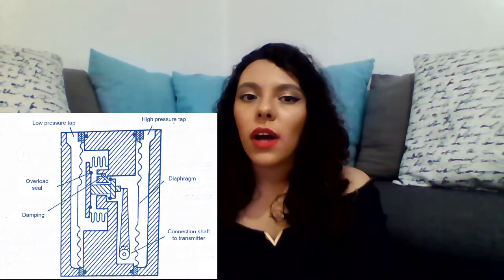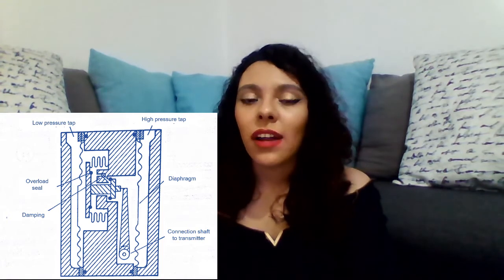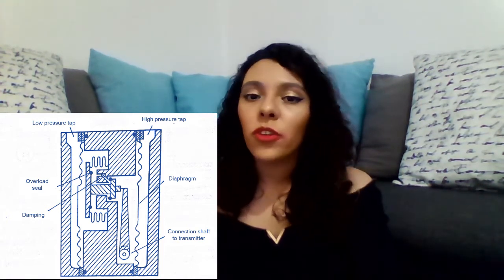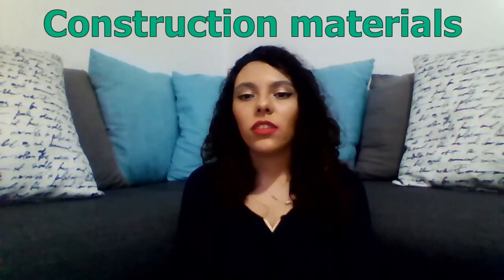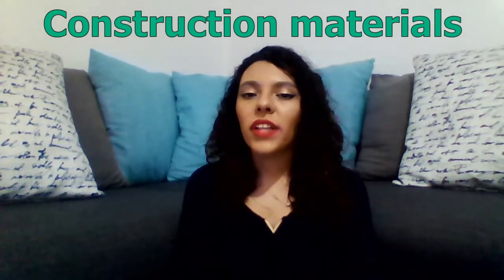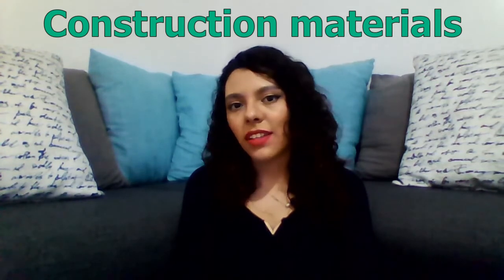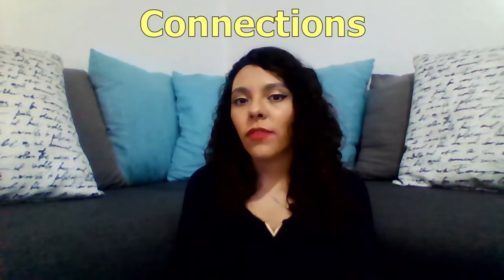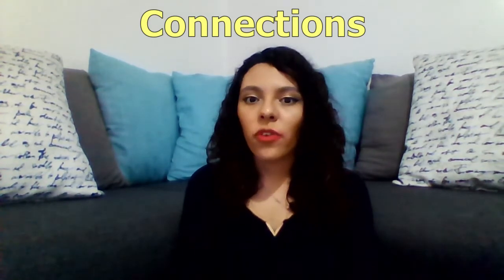The diaphragm ones are similar to the bellows ones, with the difference that the chambers are separated by diaphragms instead of bellows, which means that the volumetric displacement is almost zero. The body of these transmitters is usually made of carbon steel, stainless steel, or aluminum, while the bellows or diaphragms are of 316 grade stainless steel, with silicone as the filling liquid. The connections between the diaphragm taps and the differential pressure converter must be suitable for the fluid to be measured.